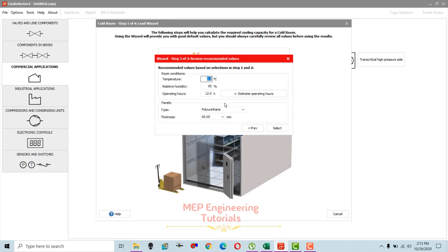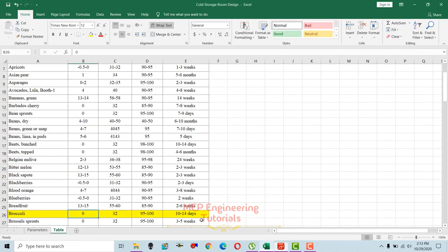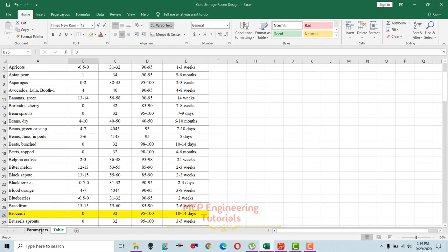The storage temperature for broccoli is 0 degrees Celsius, so change this to 0 degrees Celsius. Relative humidity is 95 to 100, so we keep it at 95. Based on this storage temperature and relative humidity, operating hours are automatically calculated — 12.6 hours. That means the refrigeration system should run 12.6 hours to maintain 0 degrees Celsius and 95 percent relative humidity. If you change RH to 98, operating hours reduce to 11.1 hours. We'll keep 95 percent and 12.6 hours.